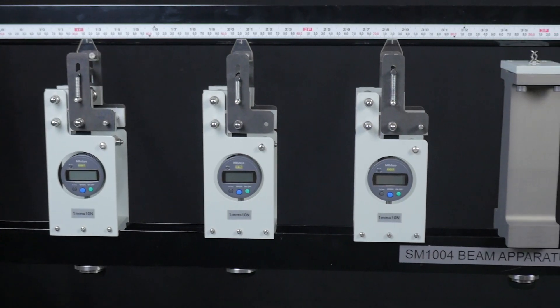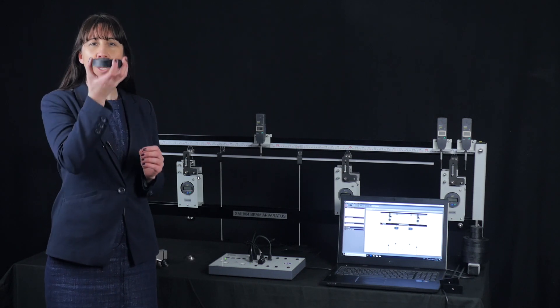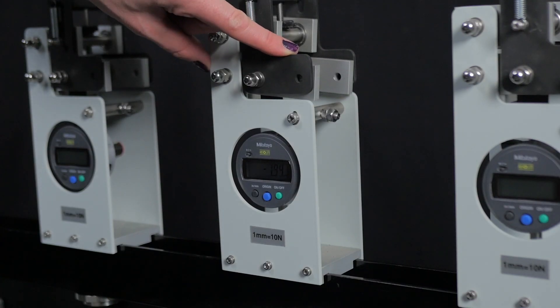There are three load cells and a cantilever support pillar that all slide along the lower member. The load cells are calibrated so that each 10 newtons of down force moves the indicator by one millimeter.